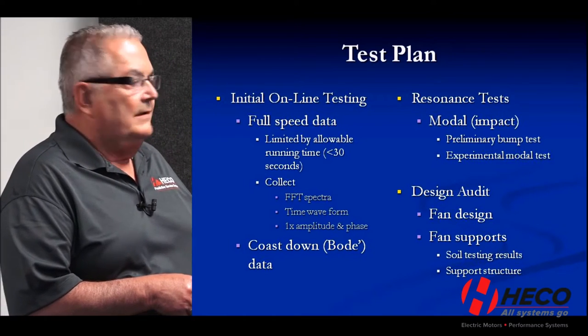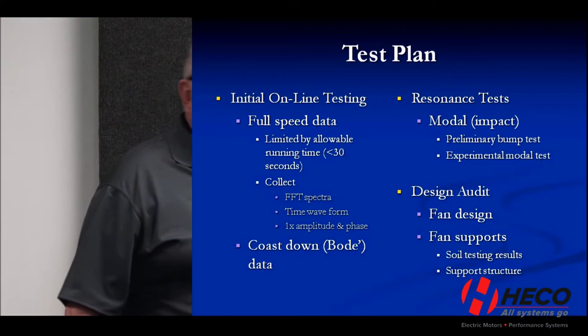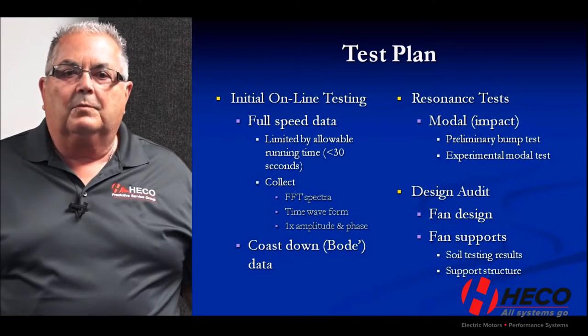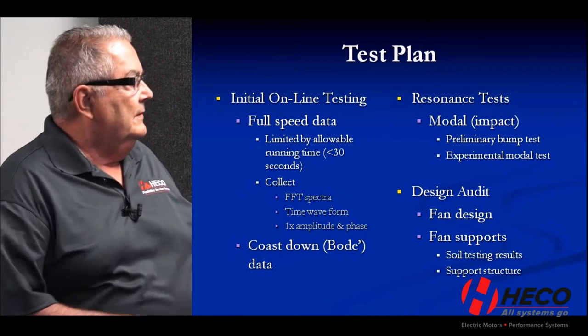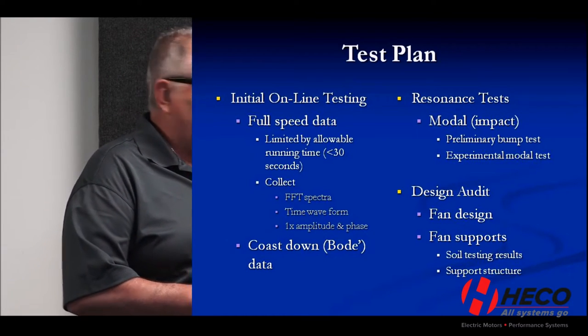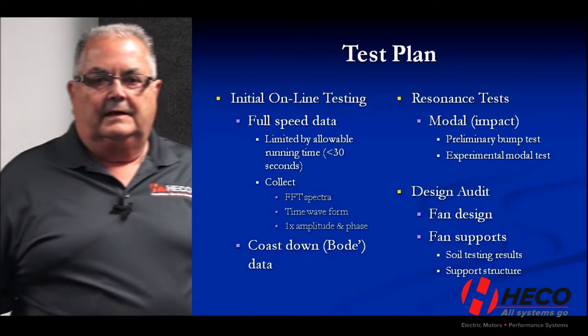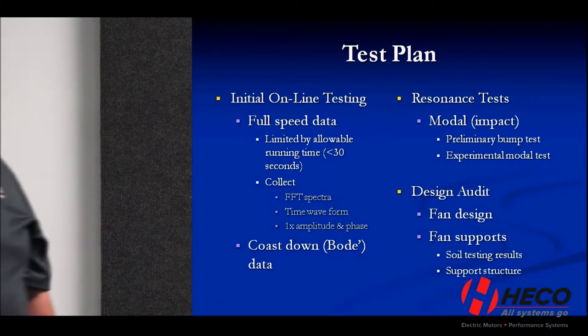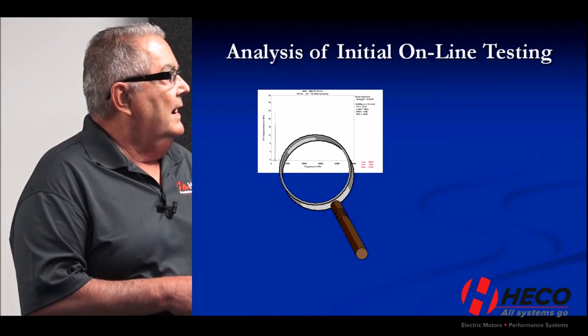We could do things like a modal or impact test — a bump test with a maybe an instrumented hammer for a full modal analysis. We also wanted to look at the identical fan that had been running for 12 months with no problems — what's different? They're supposedly identical, but nothing is ever really identical. So we said let's do a design audit: is there something in the fan design, the fan supports, the soil, or the support structure that makes this fan different from the other one?